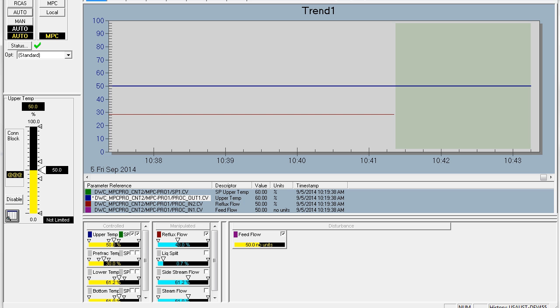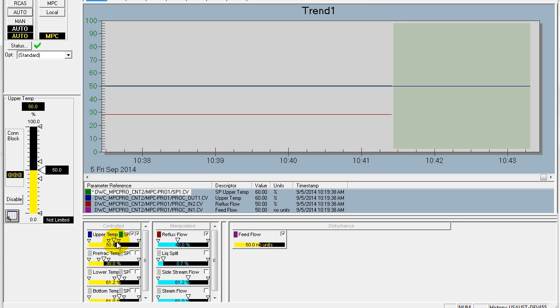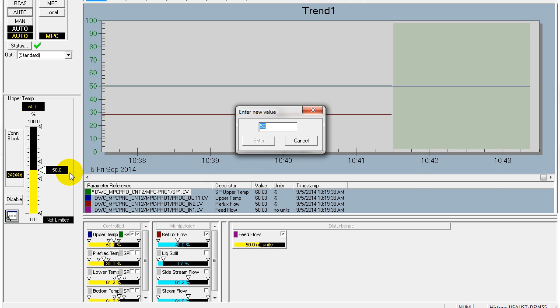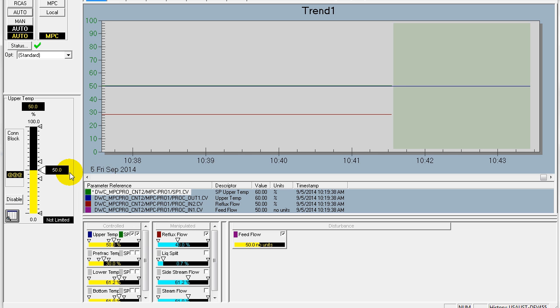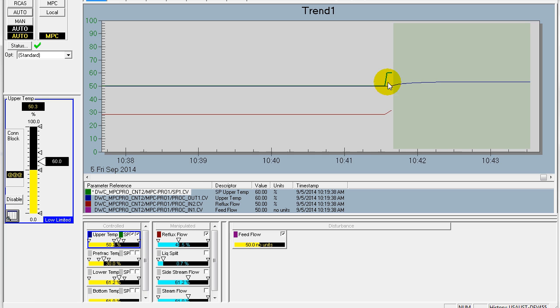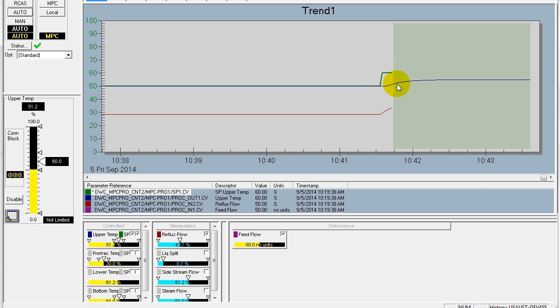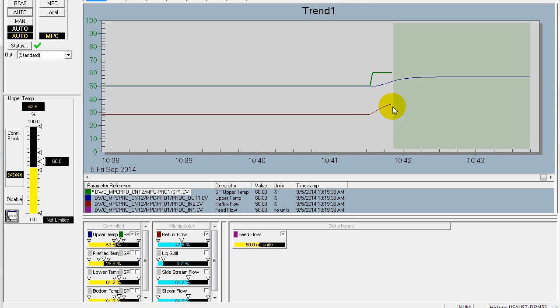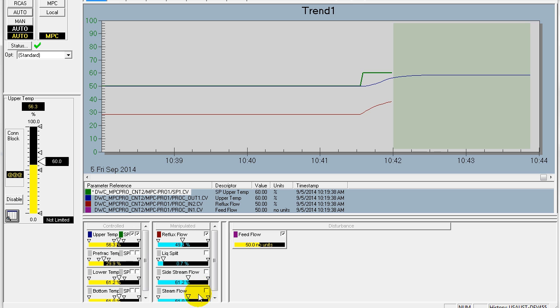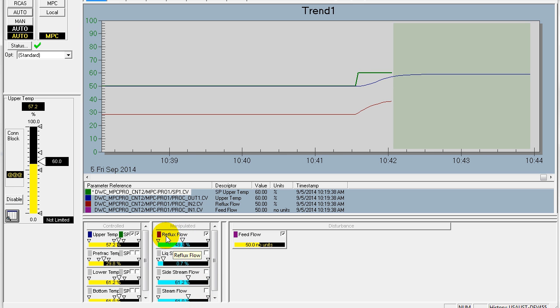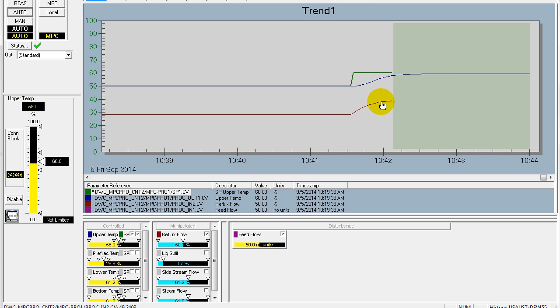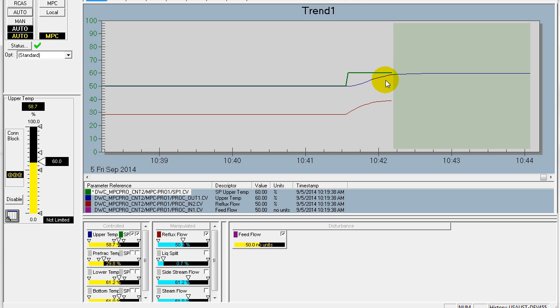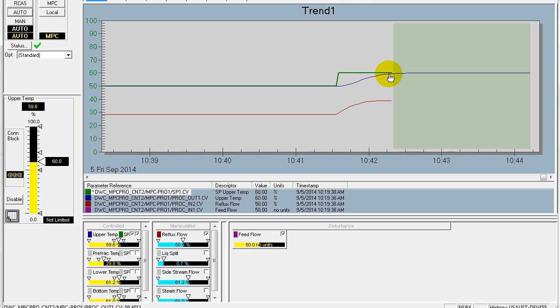We can enable the calculation. By going to our operator interface, we can select the upper temperature being controlled by model predictive control, and we'll introduce a 10% change in that upper temperature. In this case, we're using the wired measurement. As you can see, using the wired measurement we get a very smooth response in model predictive control to the setpoint change. In green, we're showing the future predicted value of the measurement. With model predictive control, we're able to independently adjust the temperature composition and position it at different points within the column without any interaction.